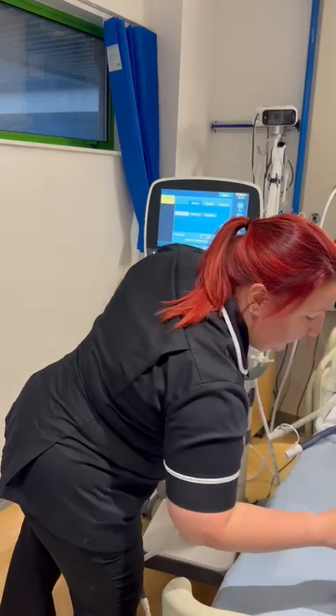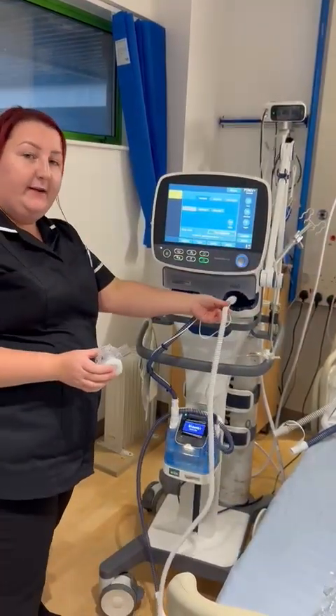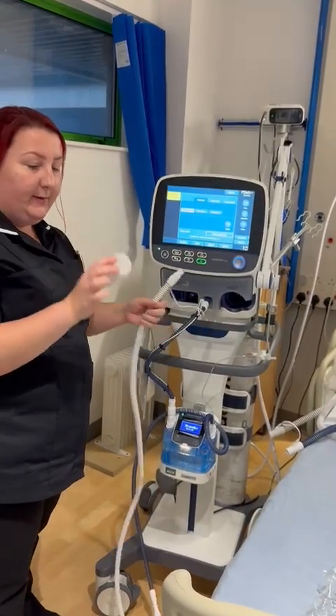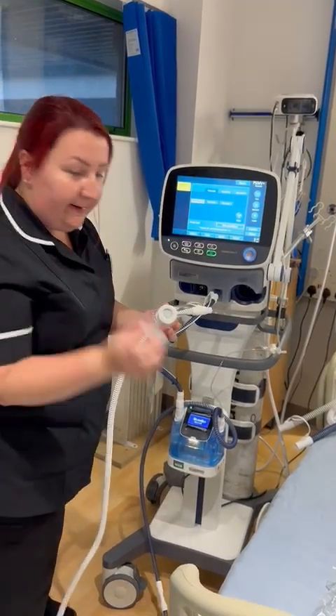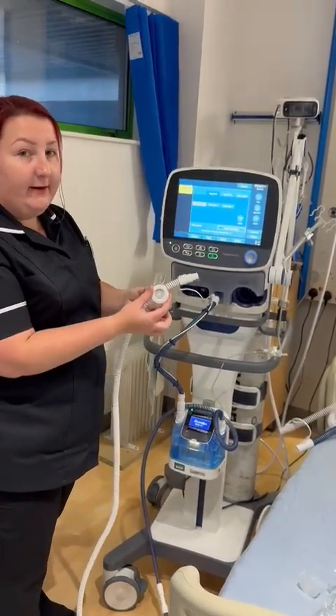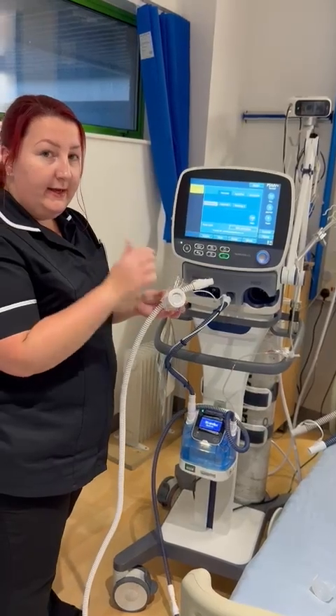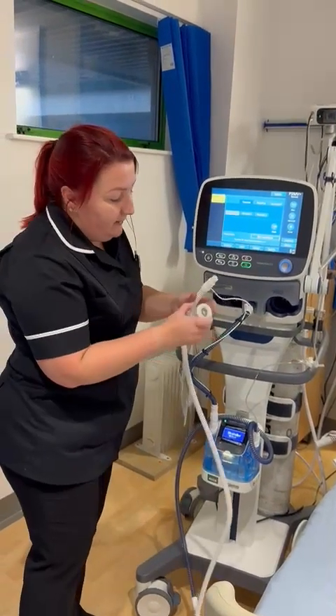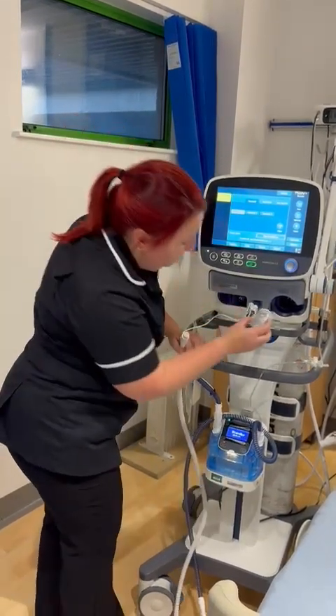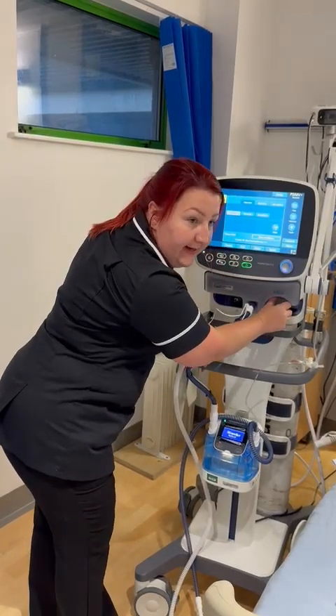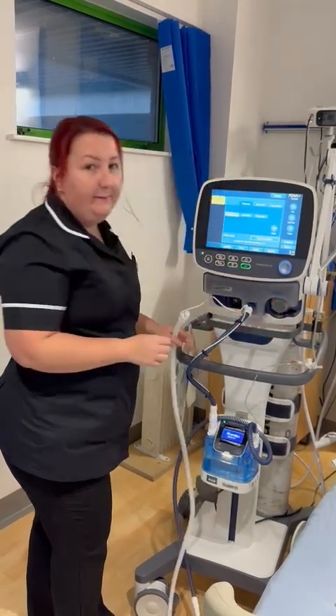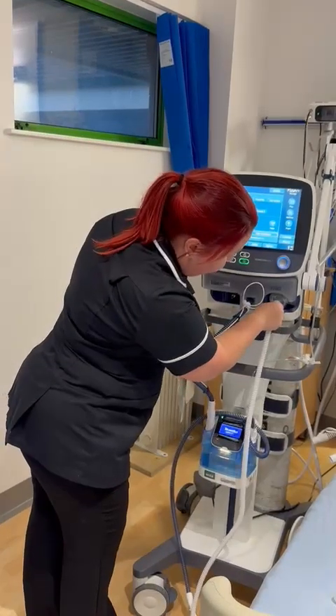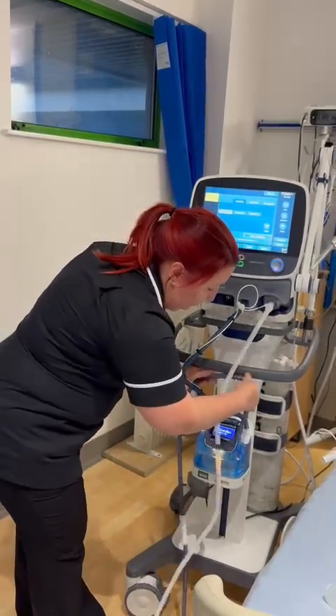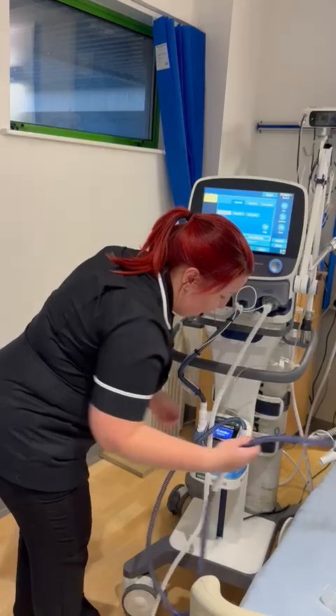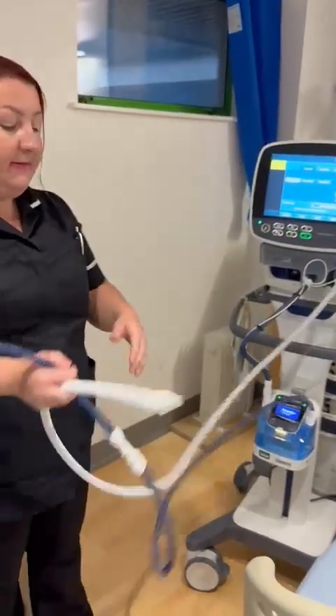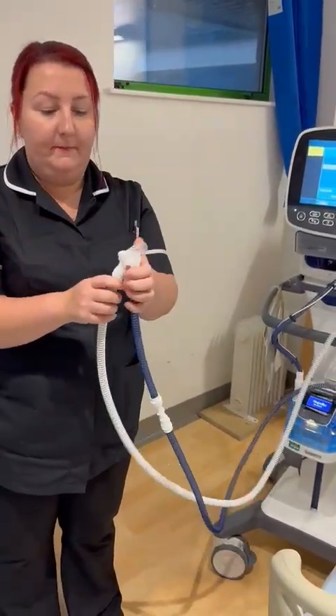Before you plug your white one in, you need an expiratory valve, which is a clear one. Take the little plastic cap off. Make sure this diaphragm is on, because if it comes loose, it won't do the pre-op checks. You literally put the diaphragm in first, and then turn it till it clicks, like that. And then you can put your blue tube in. Then these two will go to your patient.